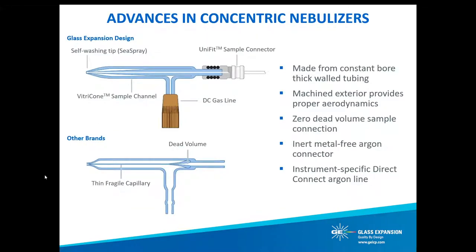Now let's examine the differences in Glass Expansion's nebulizer designs. All concentric nebulizers from Glass Expansion feature our Vitricone sample channel. Non-Glass Expansion designs typically use a hand-drawn glass sample capillary, where the internal diameter can vary, preventing laminar nebulizer flow and creating points where particulates may lodge. The Glass Expansion Vitricone sample capillary is entirely different — it's machined from a thick-walled glass capillary providing a highly reproducible geometry and constant internal diameter from sample inlet to the tip. In combination with our Unifit sample connector, this provides a zero-dead-volume sample connection.